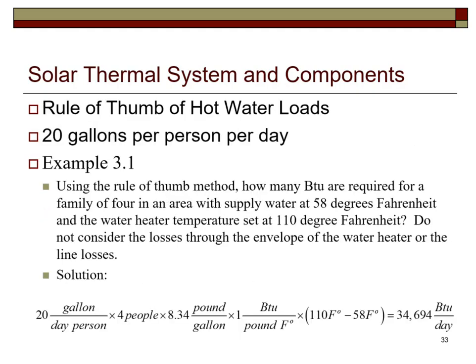The formula method for determining the hot water requirements for a family of 4 is demonstrated. 4 people using 20 gallons of hot water per day each use a total of 80 gallons of hot water. 80 gallons times 8.34 pounds per gallon, the difference between 110 and 58 degrees Fahrenheit, and the specific heat of water gives us 34,694 BTUs per day.